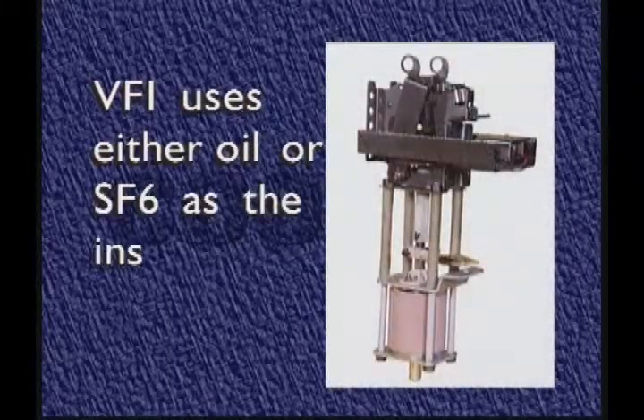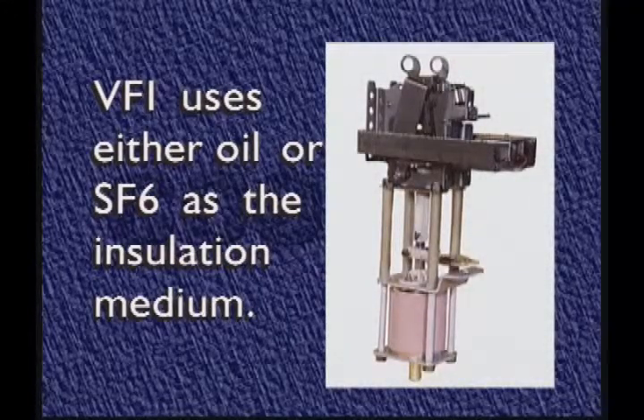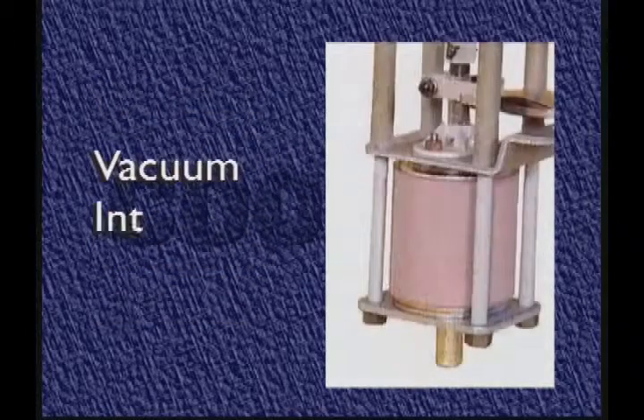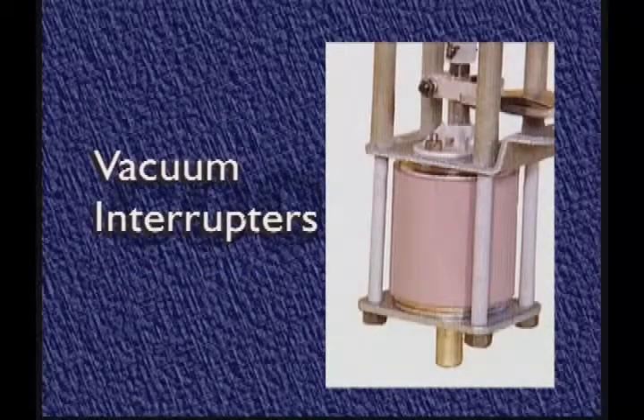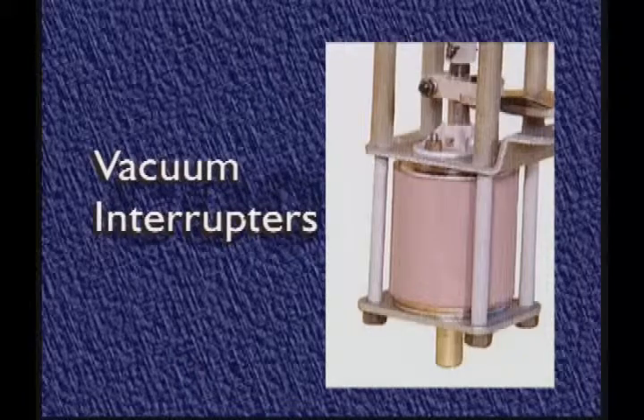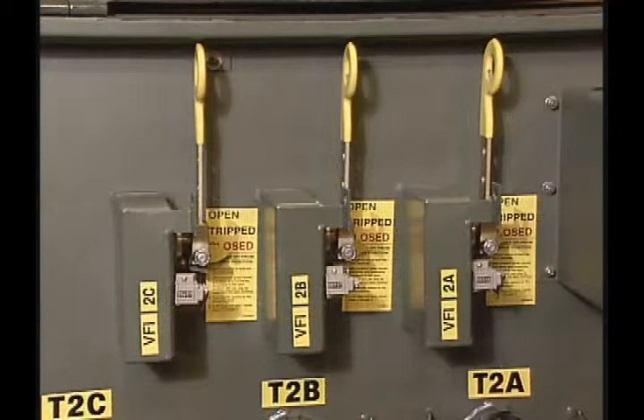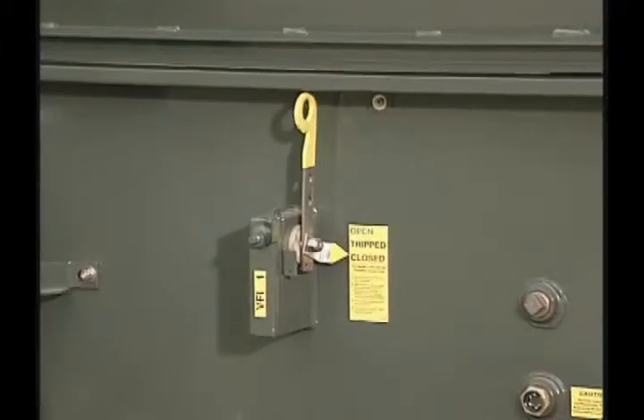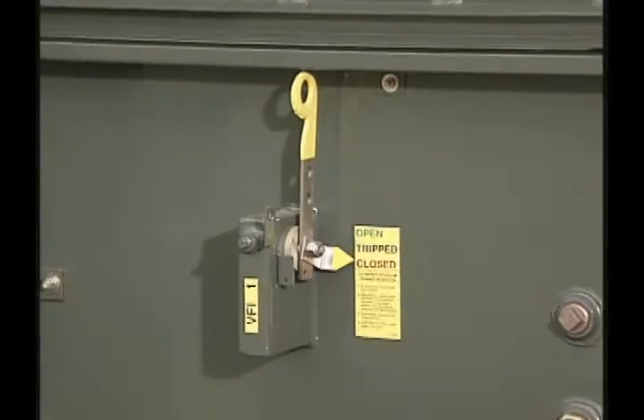VFI uses either oil or SF6 as the insulation medium. Load and fault interruption takes place within sealed vacuum interrupters, eliminating the threat of contamination to the insulating medium. The VFI has fault current interruption and load make and load break switching capabilities. The fault interrupter mechanisms can be configured for either single-phase or ganged three-phase operation.